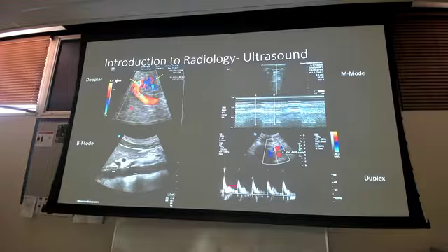This is the duplex, so the thing on the bottom here is evaluating the vasculature, kind of the pressure and the squeezing of the artery, that's what those little things are. You don't need to interpret that or read that. I mostly need you to know what mode is for what study, so that when you're using the machine for whatever reason, you are set on the right mode.